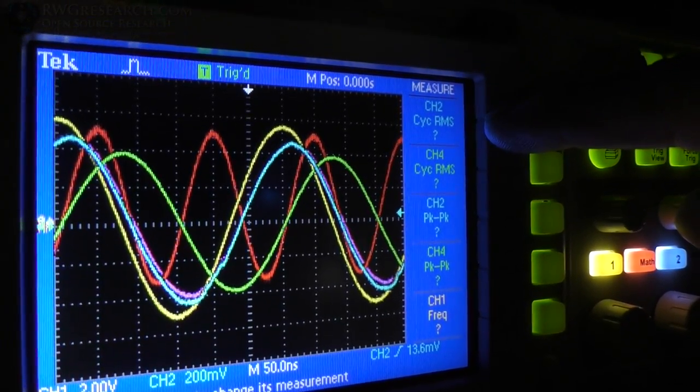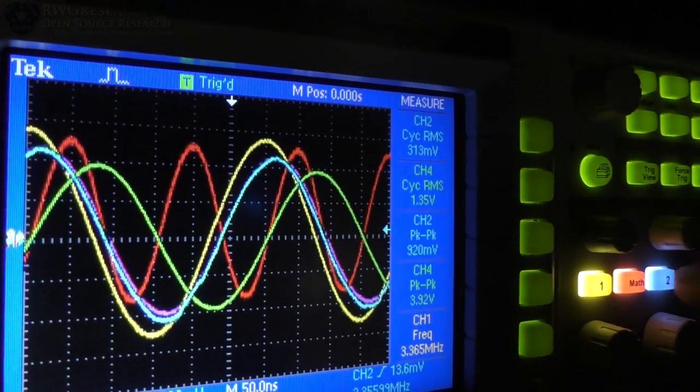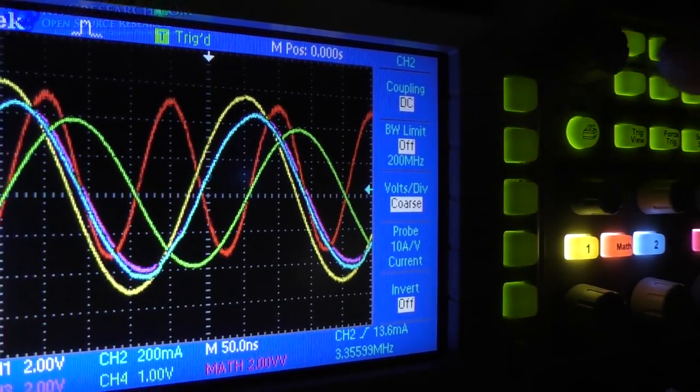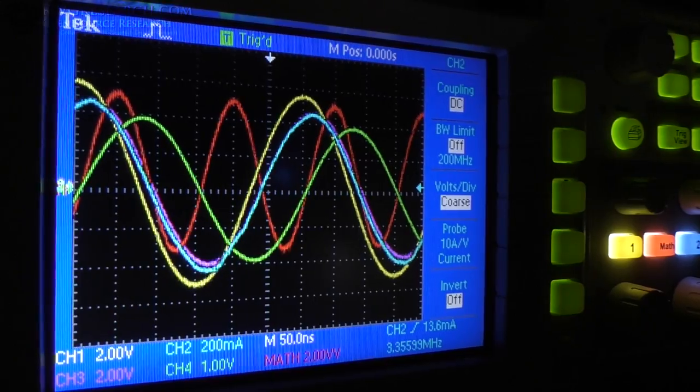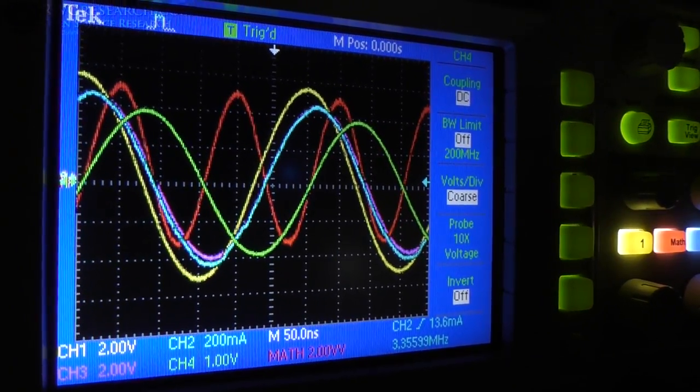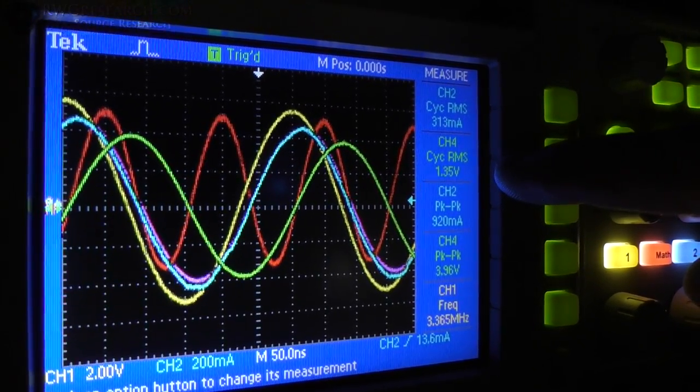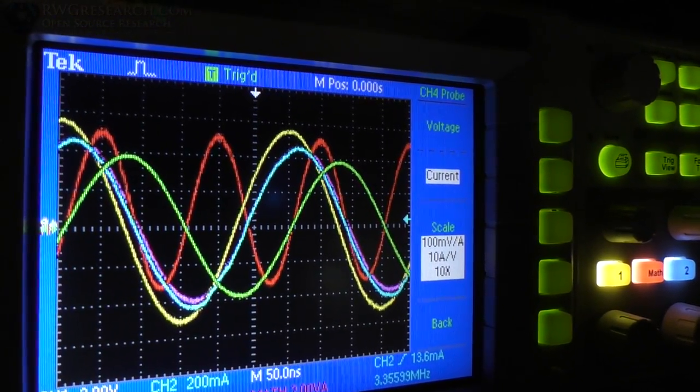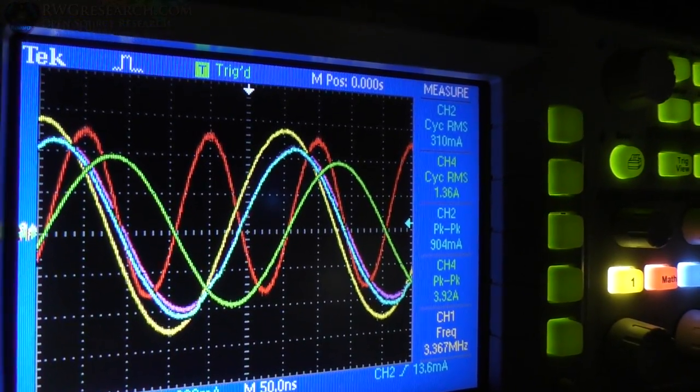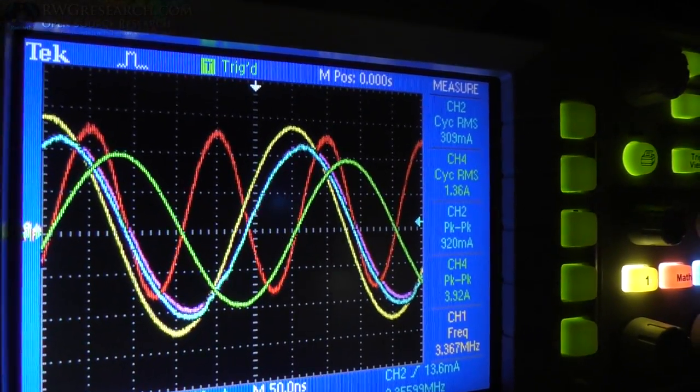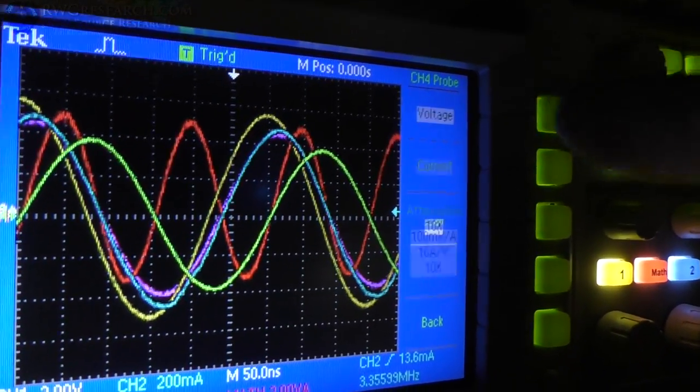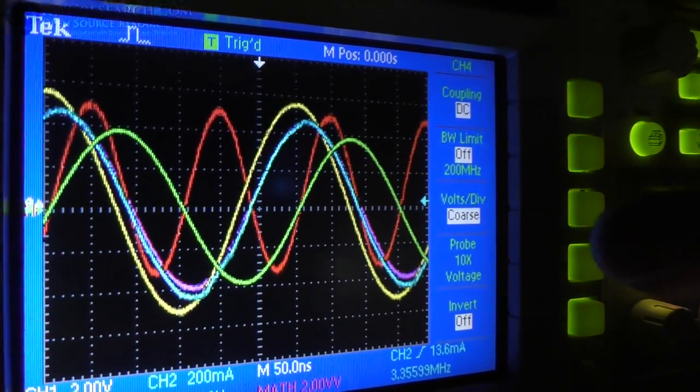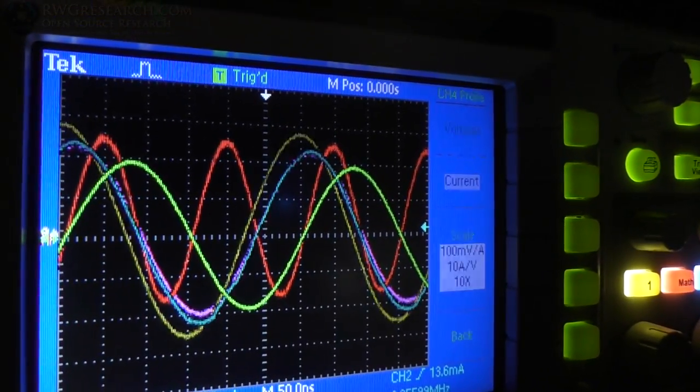I'm going to try to hold this steady for you because I want this to be clear. So what I've got is all voltage measurements currently, but I'm going to switch these probes. So channel two is across L1. Channel four is across L2. You can see I have the equivalent numbers is what I have on my screenshot here. So we're at the same place. And I'm just over on frequency. But in my video, I showed that this is actually a better frequency. I was just demonstrating something different there. So what we're going to do is we're going to go to channel two, and we're going to switch this to current. It's on 100 millivolts per amp. So if there's any scaling to do, up or down, then you'll need to do that. Currently, it is scaled, I believe. So just remember that this is scaled differently. So the true power ratings later is actually going to be the decimal place is going to be moved around. But the numbers are correct. Don't worry about the scaling. Just know that they're equal.